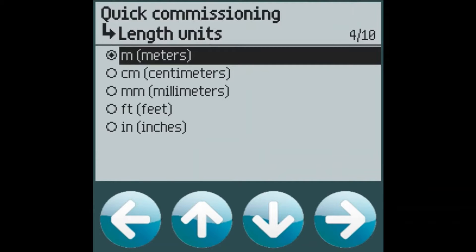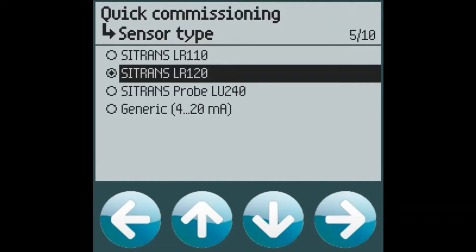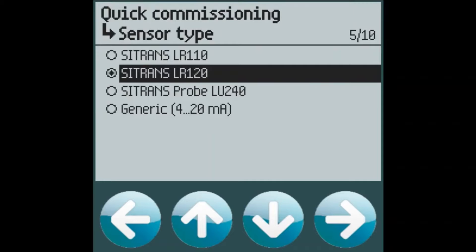The customer wants to measure in meters which is the default and the LT500 will automatically detect any smart sensors which are connected to the device. In this case the customer has elected to use the SITRANS LR120 radar transmitter which is ideal for wet wells with its narrow beam angle.